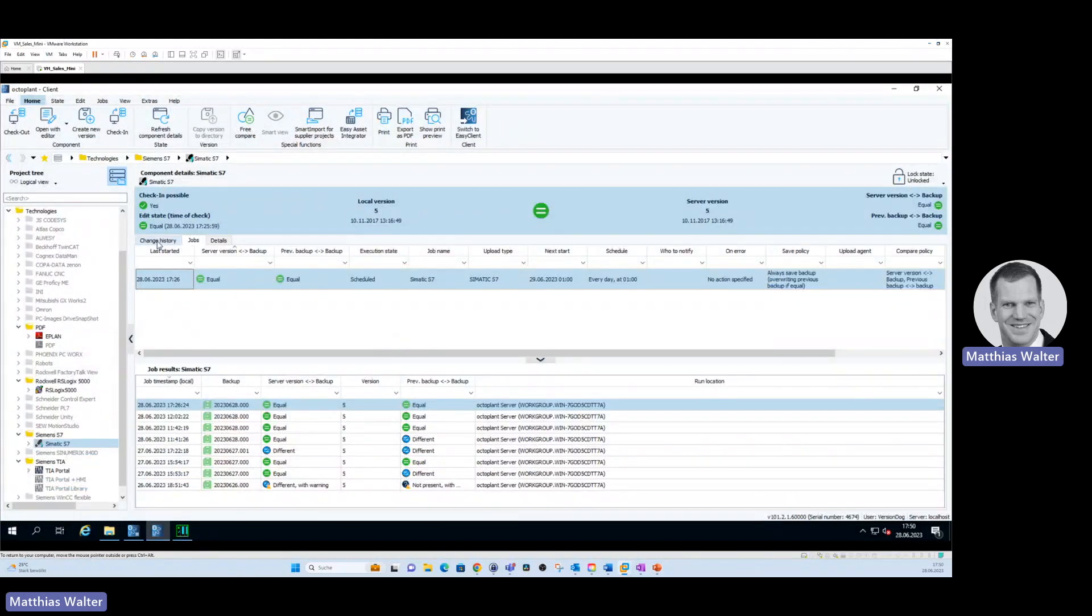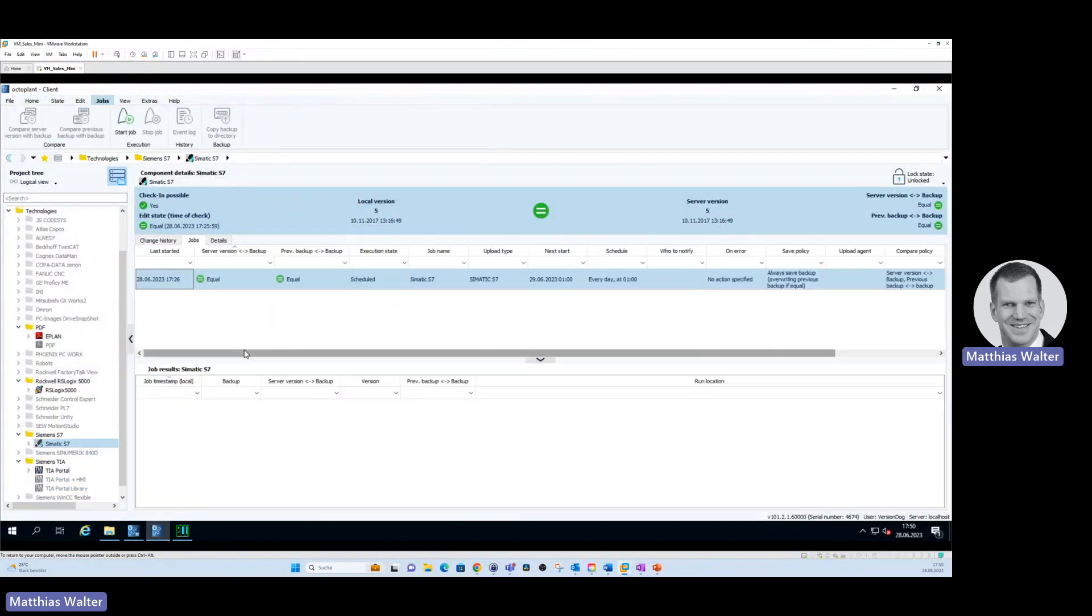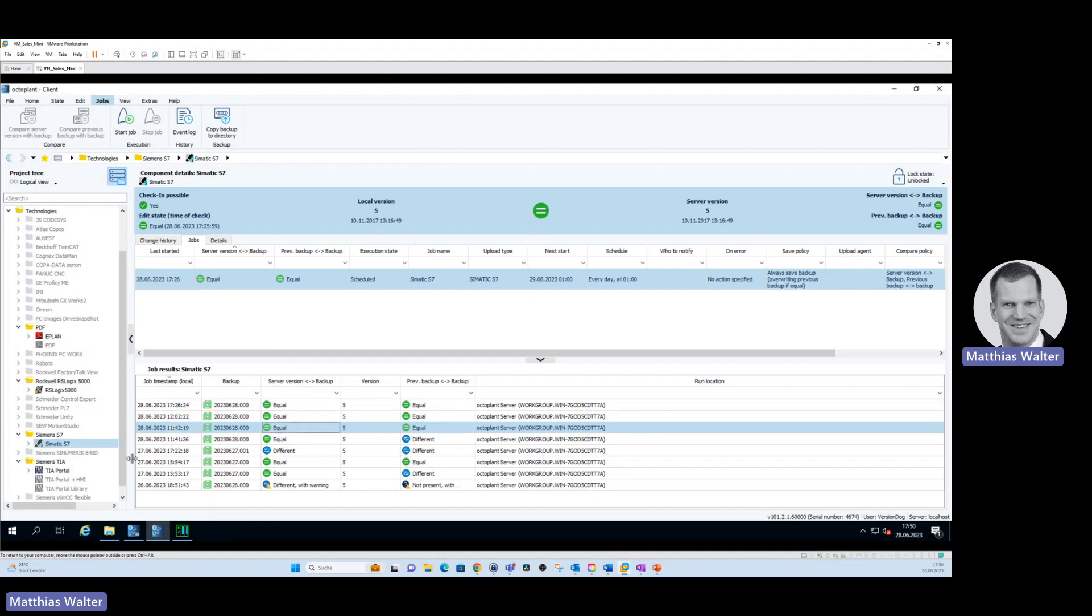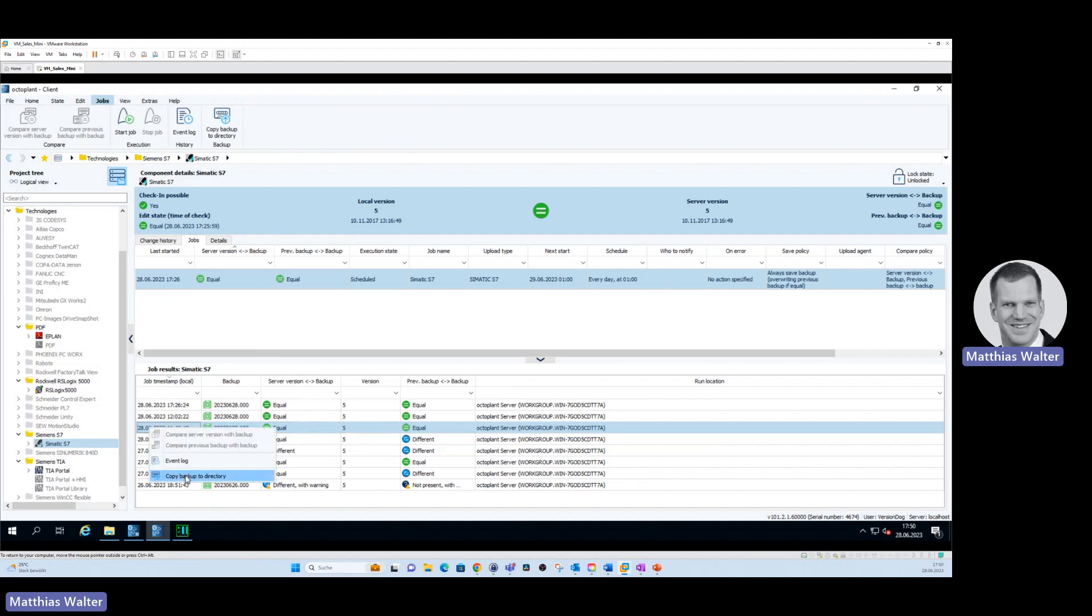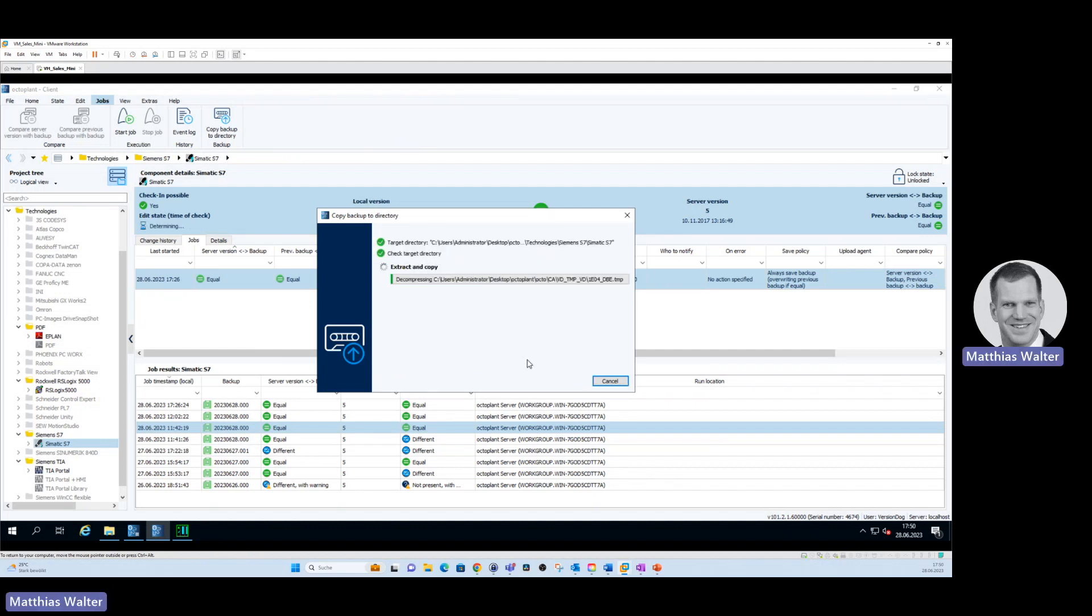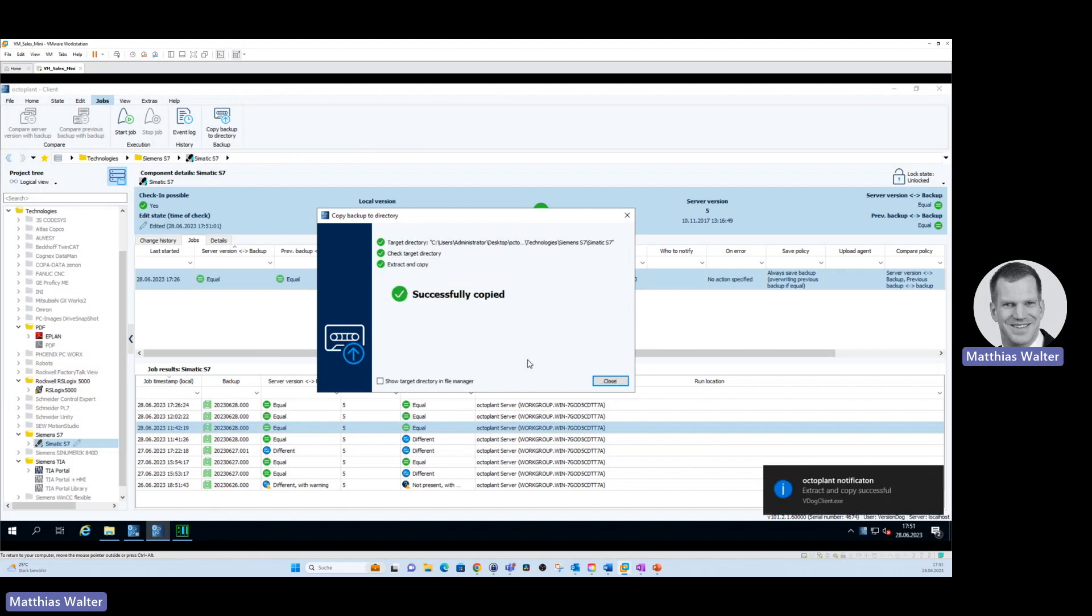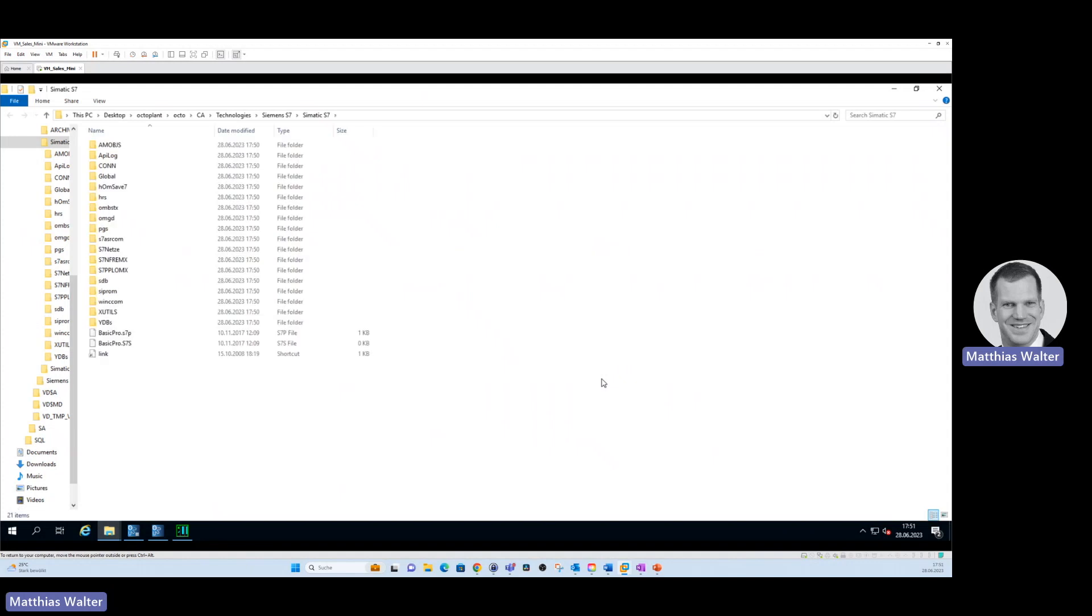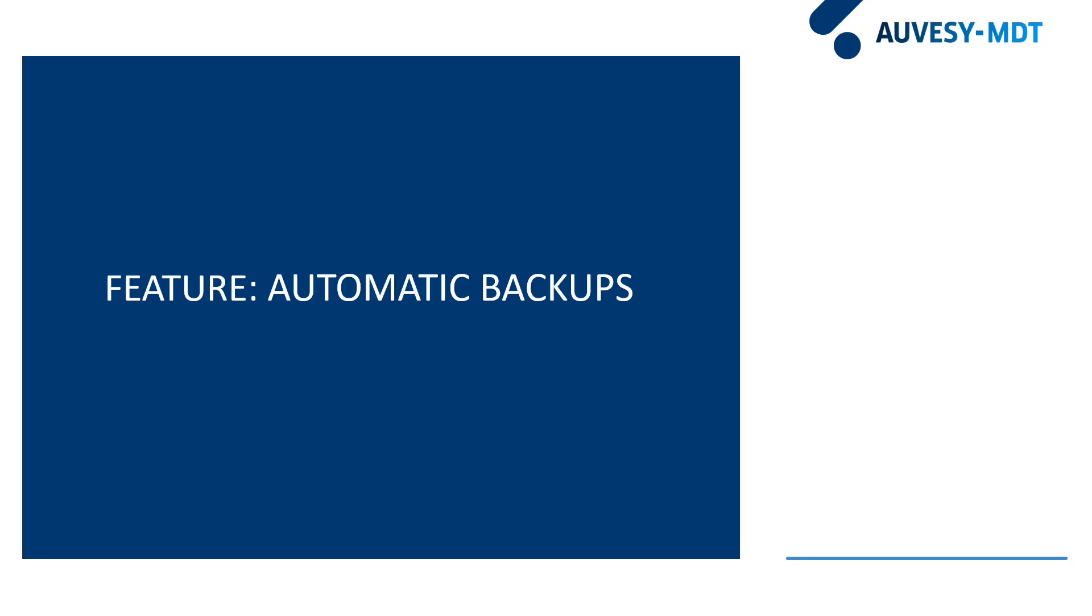Here you see if you click on jobs, a history of the already performed jobs by the software. You just remember the point when everything in your production facility worked fine. Let's, for example, pick this one here from the list. You click on it and say copy backup to directory. You click on next and now OctoPlant is restoring this backup and will copy it to the directory. If you now click show target directory in file manager and click on close, the directory will directly open and show you the whole program, the whole PLC code. With that PLC code, you can create a new version. You can directly go to the editor. You can directly upload it to the PLC. The whole programs are saved here.